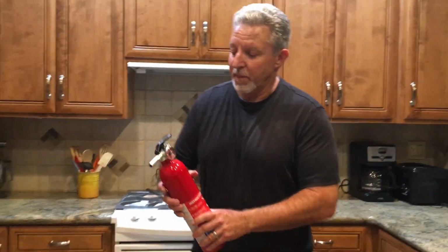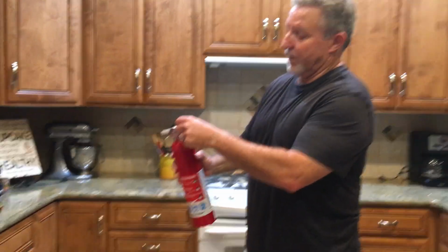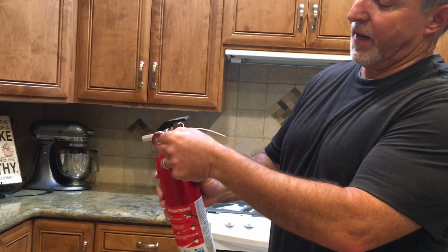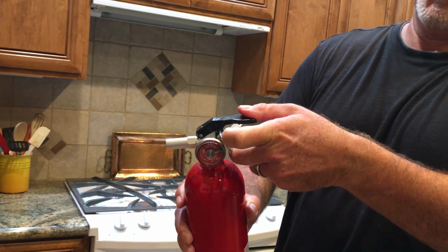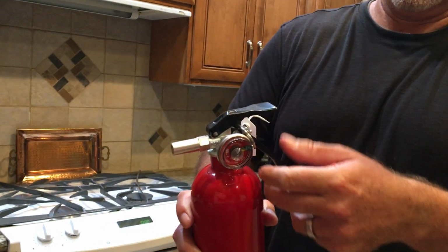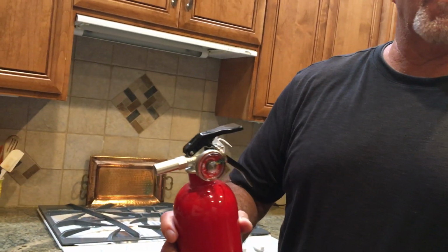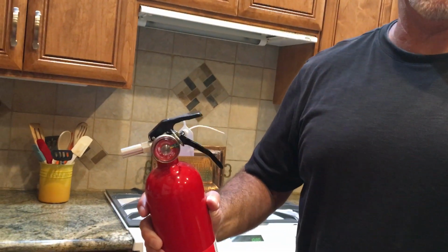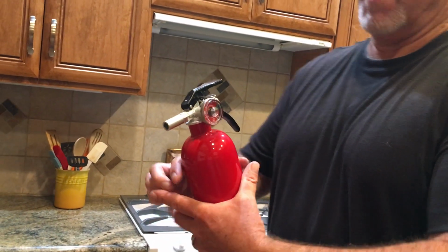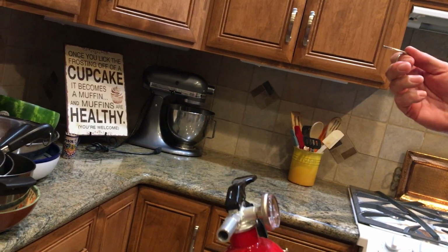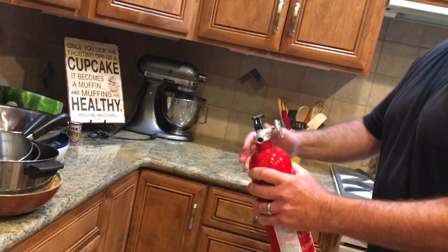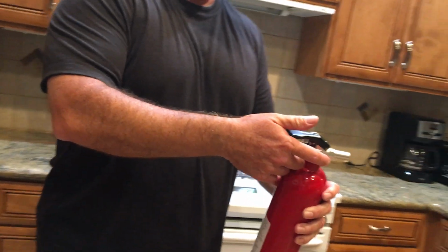Should you decide to fight the fire, if you notice on the fire extinguisher, there's a ring, a pin, and the pin keeps me from being able to discharge the extinguisher with the handle. So the first thing you do, you want to remember the acronym PASS, P-A-S-S, okay? PASS: you're going to grab the pin and it's got a strap on it, a keeper, that will break. You pull the pin out, okay? Now you're able to activate the fire extinguisher.